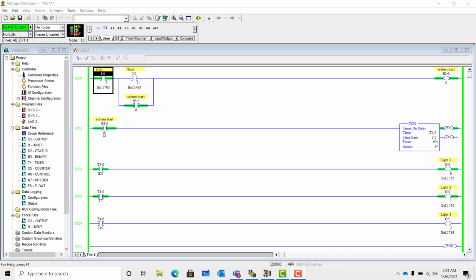All right, as you see, we've turned on our bit and we're started counting. As soon as we turned on this bit and enabled this timer, this bit goes true, turns on this output according to this program. As it's counting, only while it's counting, the timer timing bit has a 1 in the bit box, and we've turned on this output according to our program.